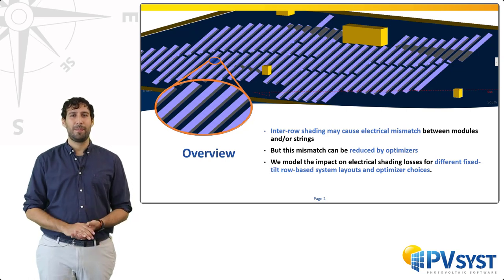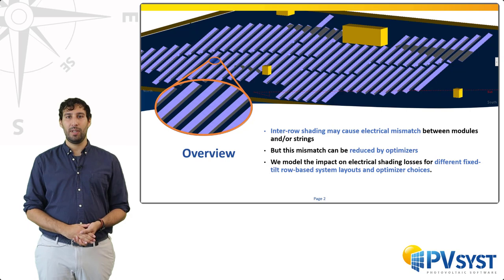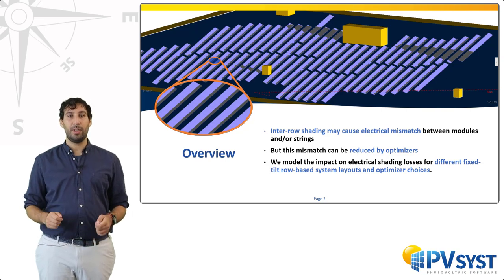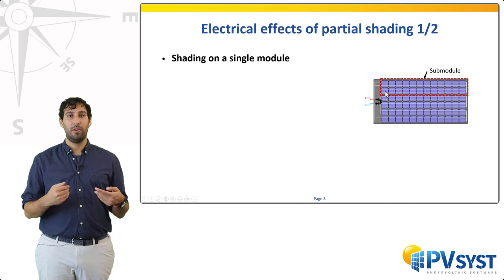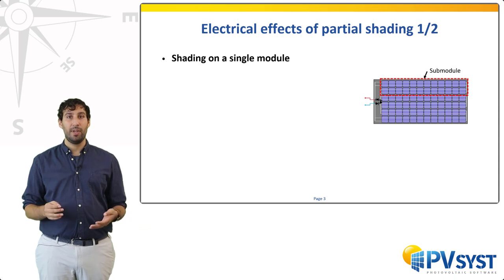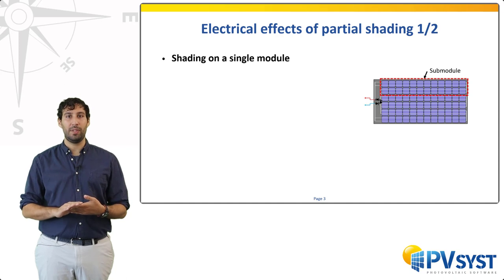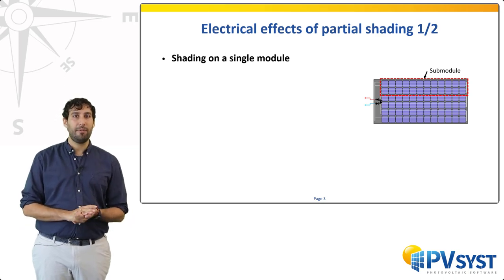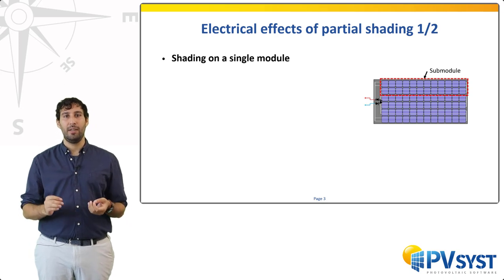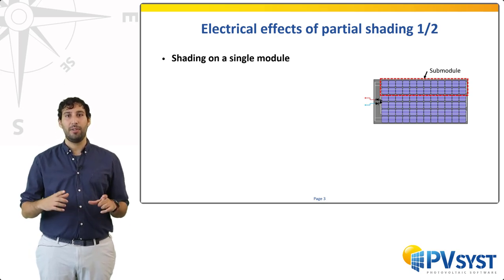Let us begin with the simplest case: the effect of shadings on a single module. The first observation is that whether one shades one cell or several cells within the same submodule, the resulting IV curve will look roughly the same. Here, a submodule is defined as a collection of cells in series protected by a bypass diode. This behavior is characteristic of components in series, as any current limitation will affect all components. Most of the modeling philosophy in PVSyst is therefore based on defining the fundamental unit of shading as a submodule, rather than the single cell.